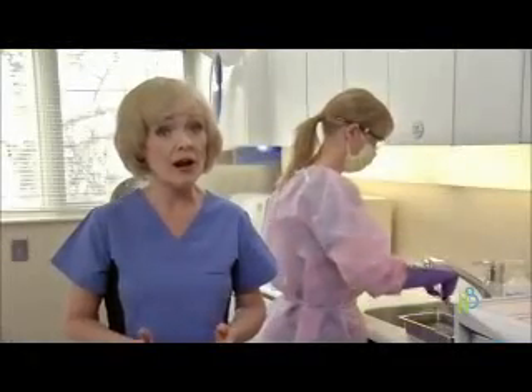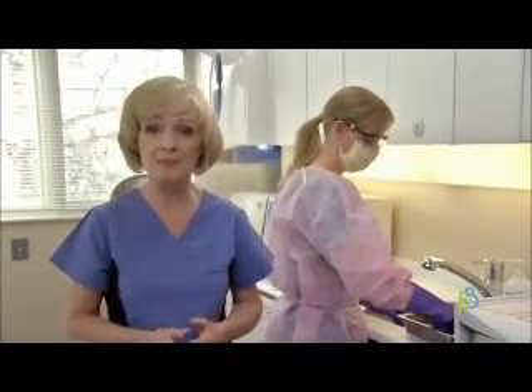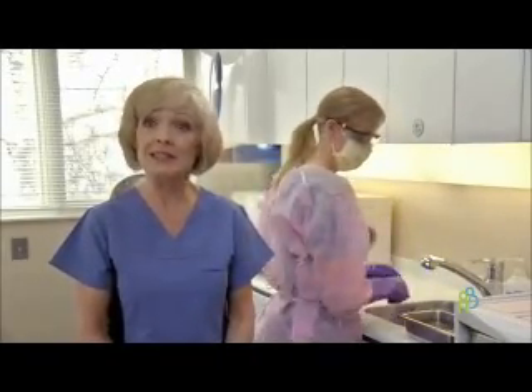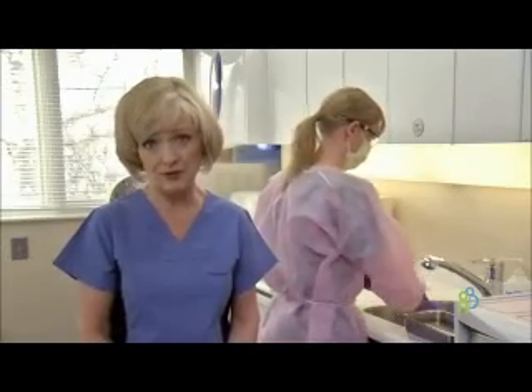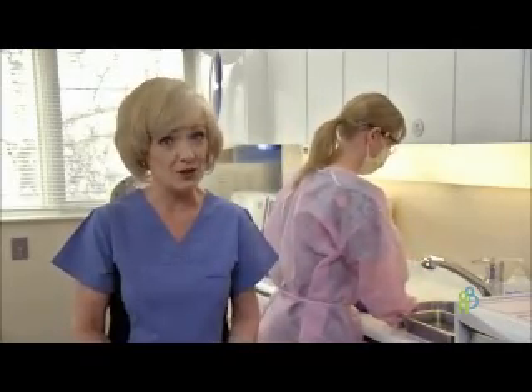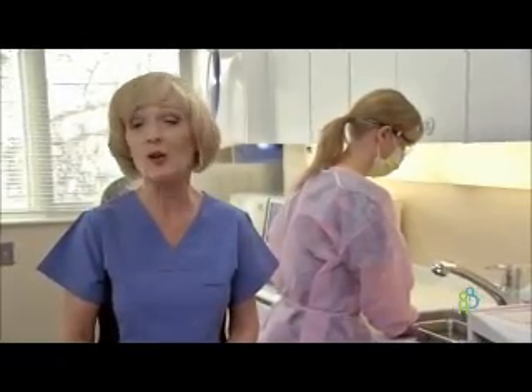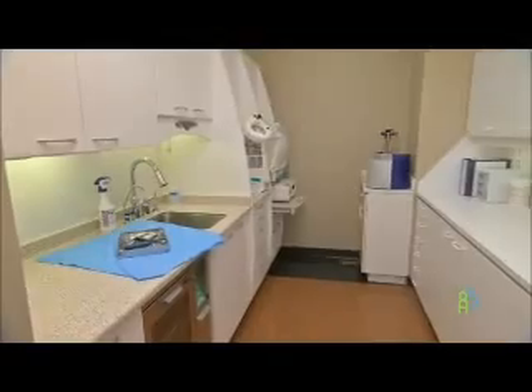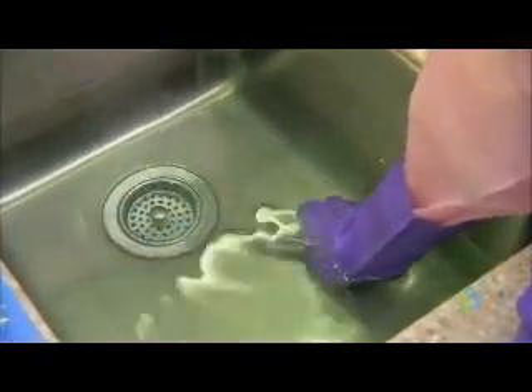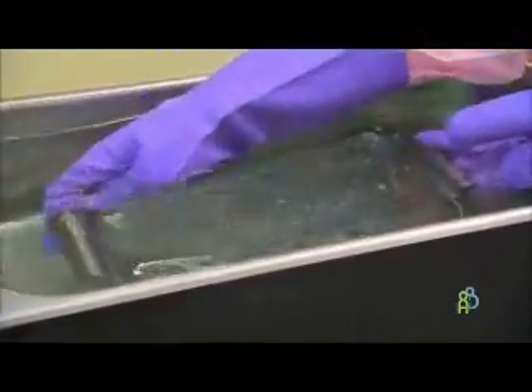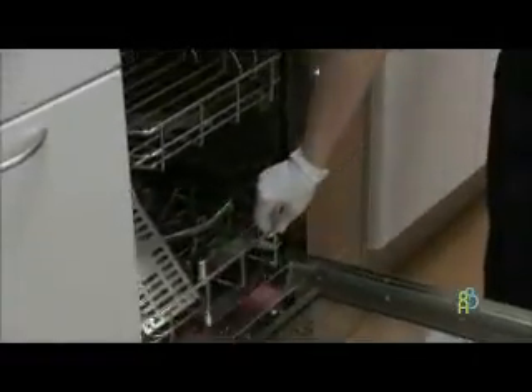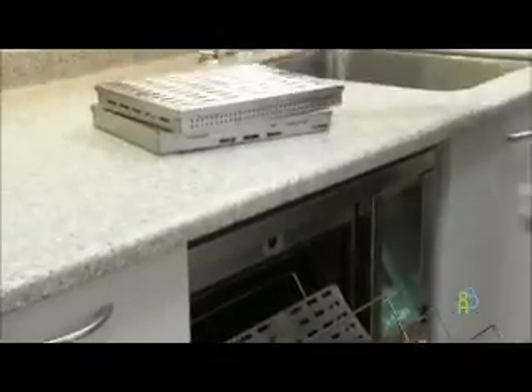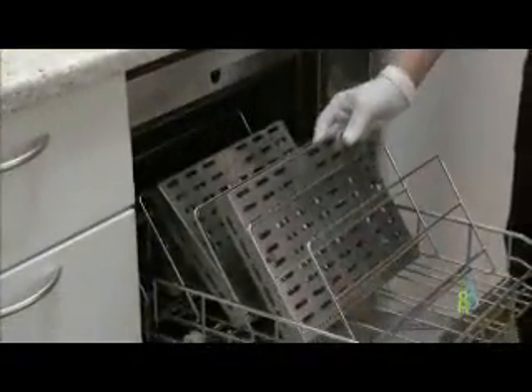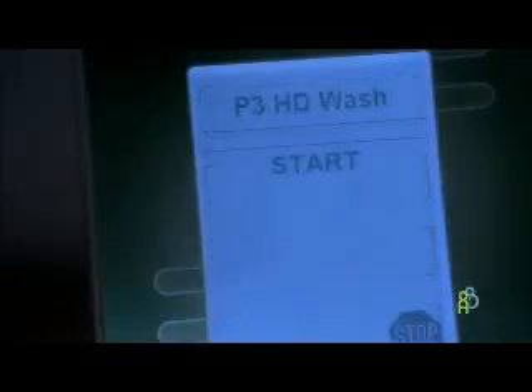For devices that are soaked prior to cleaning, soaking should occur for the shortest time possible, as prolonged soaking can result in damage or lead to the development of biofilm that can protect organisms from sterilization. Dental devices must not be left soaking overnight. Depending on the setup at your reprocessing area, you'll either be cleaning devices manually and using an ultrasonic cleaner, or operating an automated instrument washer. When using an automated instrument washer or washer disinfector, the manufacturer's instructions for installation, use, and maintenance must be followed. Household or commercial dishwashers are not appropriate.